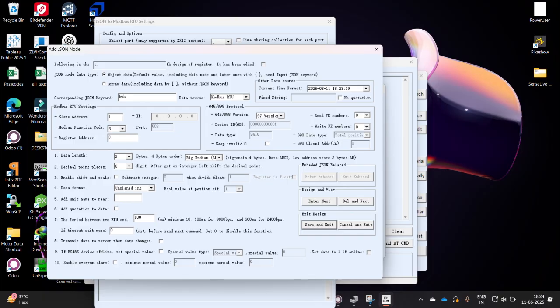My hardware communicates to my gateway via Modbus RTU, so I've selected that. There are 4 types of function code. As you know, the holding register contains function code 3, and the input register has function code 4. I'm selecting 4, and my register address is 1. So for kWh, I'm going to read the first register address. Here you can see the byte setting, for the data length I need to select 4, as I have a 32-bit float. So 4 bytes means 32-bit. That's the 4 byte I've selected, and big endian is my pattern.